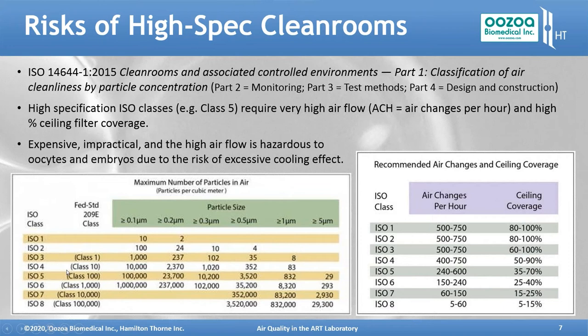So if you want to go to ISO class 5, which is like a class 100 clean room, which is very clean, like a laminar flow operating theater, for example, the recommended air changes and ceiling coverage for class 5 is 240 to 600 air changes per hour. That's more than a gentle breeze. And the ceiling coverage is 35 to 70%, which means that the recommendation is that between a third and two thirds of the ceiling area is actually HEPA filters. So that's a very difficult thing to achieve. It makes these sorts of high spec clean rooms expensive, impractical for our purposes as for ART labs, and the high airflow is hazardous for oocytes and embryos due to the risk of excessive cooling effects caused by that breeze. That breeze is only room temperature air by definition.